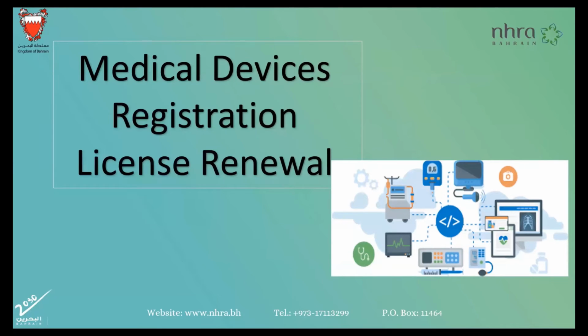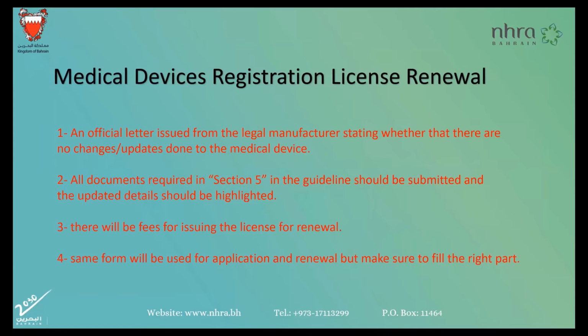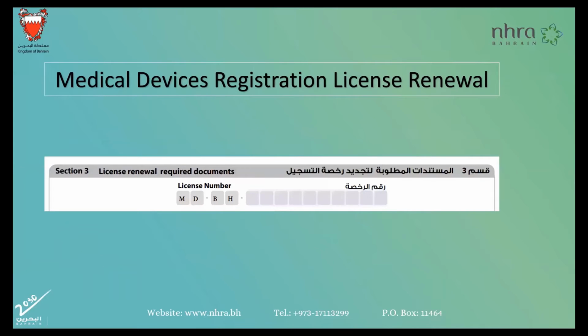For medical device registration license renewal, the requirement is, first, an official letter issued by the legal manufacturer stating whether there are no changes or updates done to the medical device. Second, all documents required in Section 5, which is in the application form and the guideline, should be submitted with updated details, such as expiry certificates. There will be fees for issuing the renewal license, and the same form is used for application, renewal, and variation, as I said before. Here is the part for renewal, and you can write the license number.